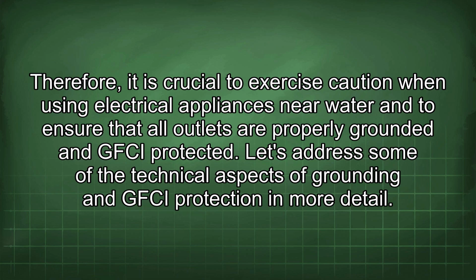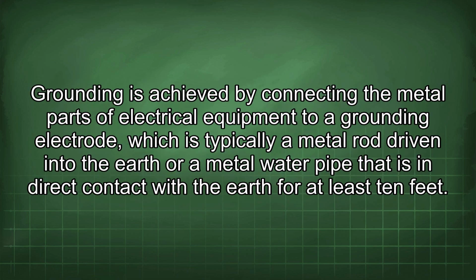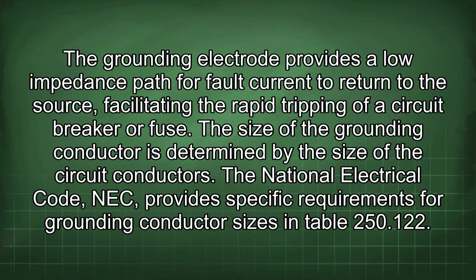Let's address some of the technical aspects of grounding and GFCI protection in more detail. Grounding is achieved by connecting the metal parts of electrical equipment to a grounding electrode, which is typically a metal rod driven into the earth or a metal water pipe that is in direct contact with the earth for at least 10 feet. The grounding electrode provides a low impedance path for fault current to return to the source, facilitating the rapid tripping of a circuit breaker or fuse.